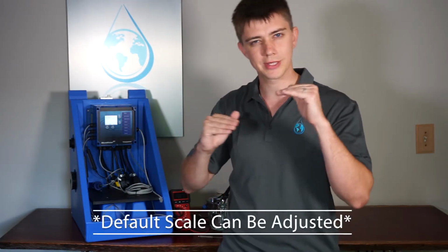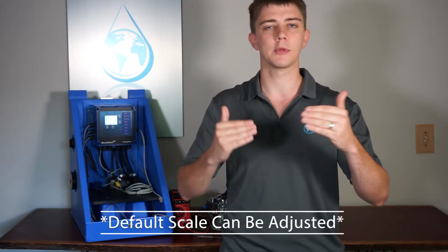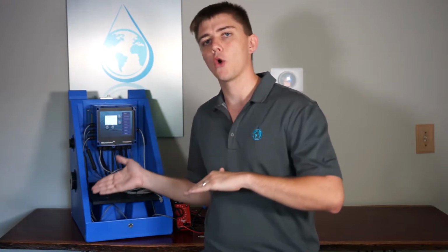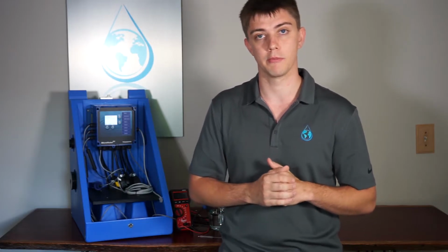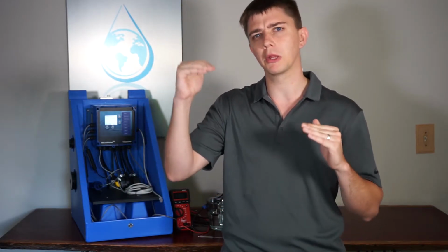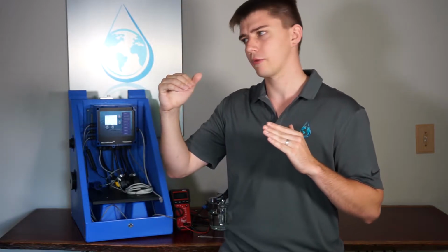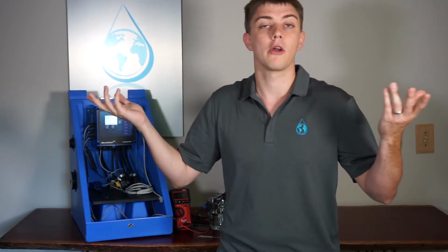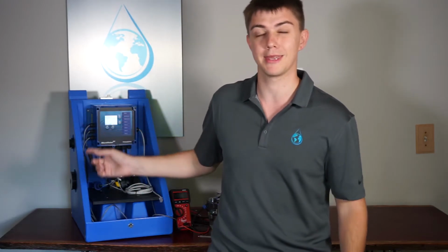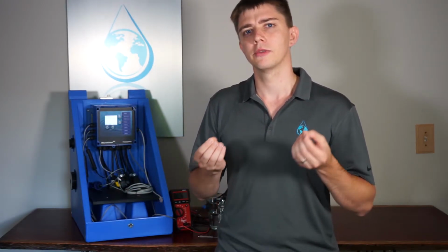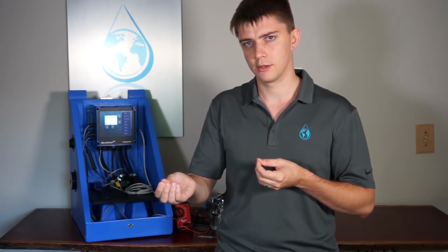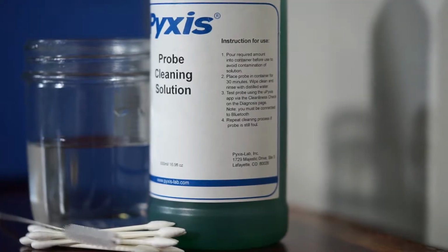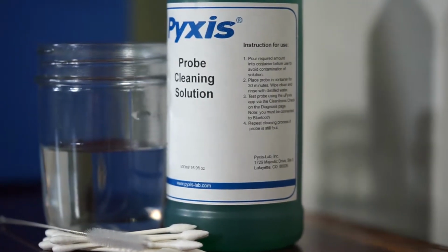Control range on the controller is typically around 100 parts per billion. That chemistry can vary based on your treatment profile, but you should be seeing around 12 milliamps when you're close to 100 parts per billion. It's important to familiarize yourself with that scale, because if your controller thinks it's seeing 175 parts per billion, but you're only seeing maybe 8 milliamps, something's wrong with your calibration. You need to pull the probe, inspect it, ensure it's clean, and probably be resetting your calibration as well.